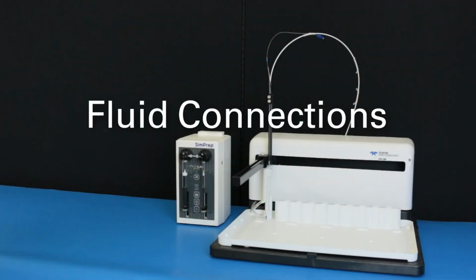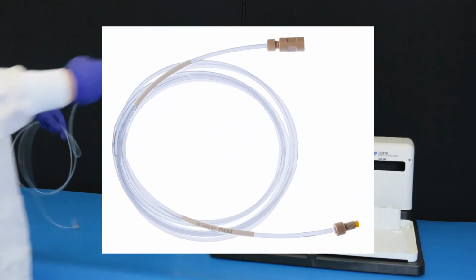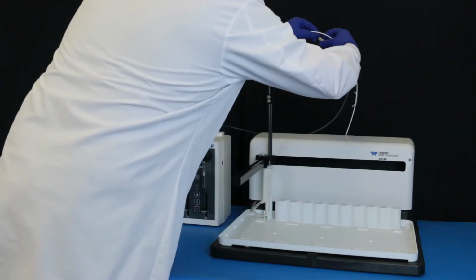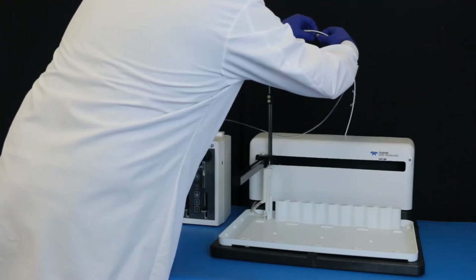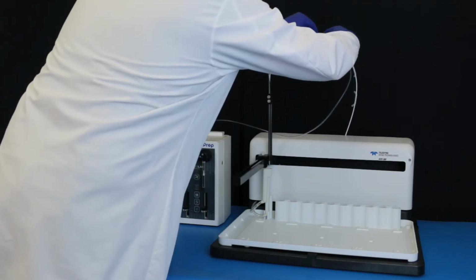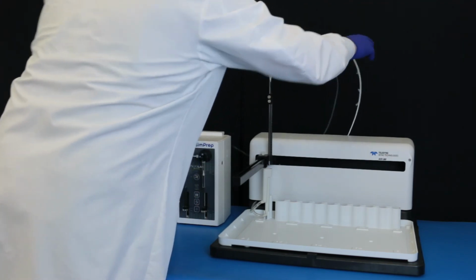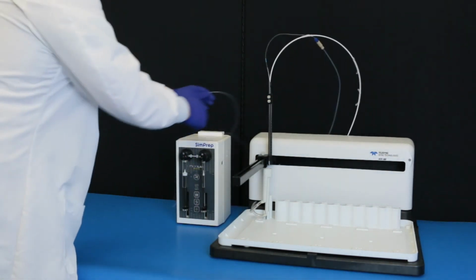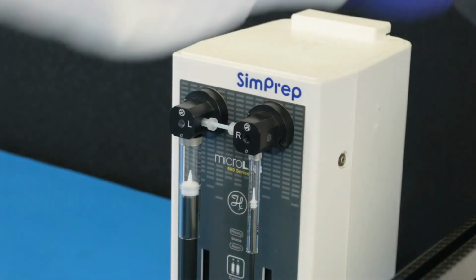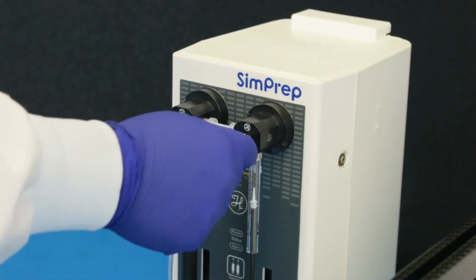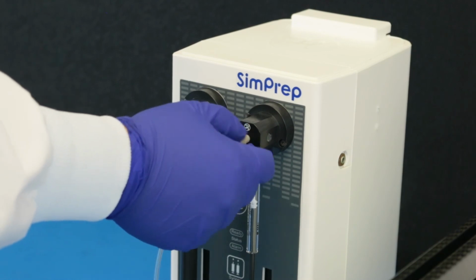Fluid connections. Identify the syringe to probe tubing. Fittings are pre-installed at both ends. Connect the sample probe to the threaded coupler. Connect the other end of the syringe to probe tubing to the front center port of the right valve on the syringe module.